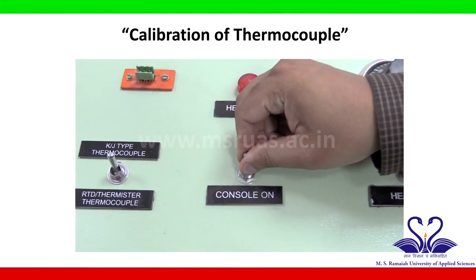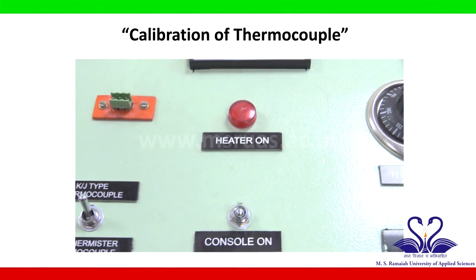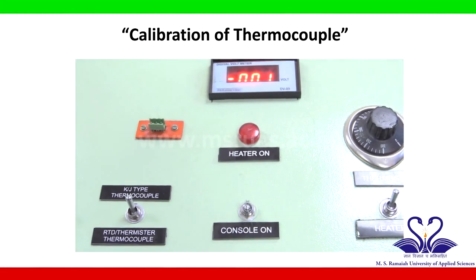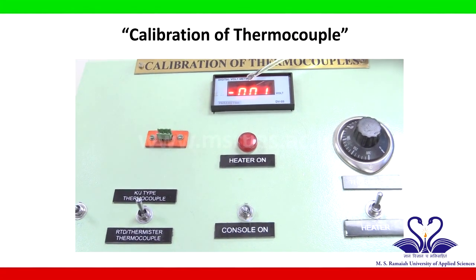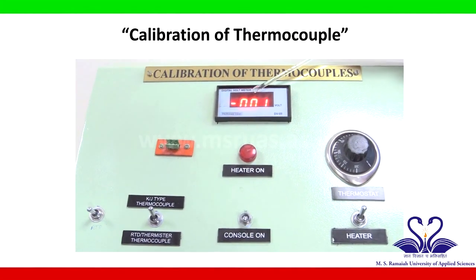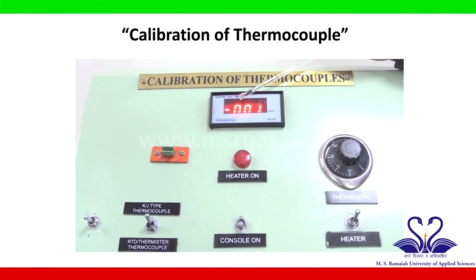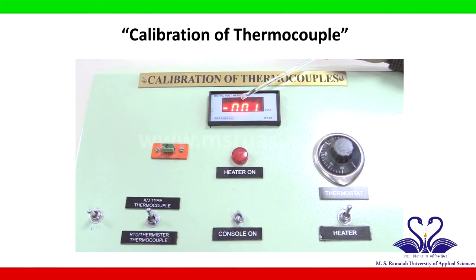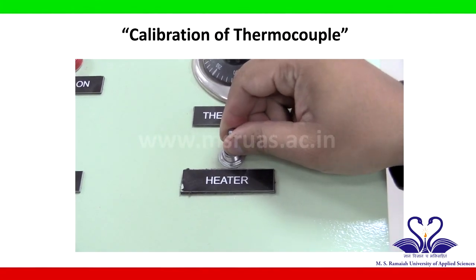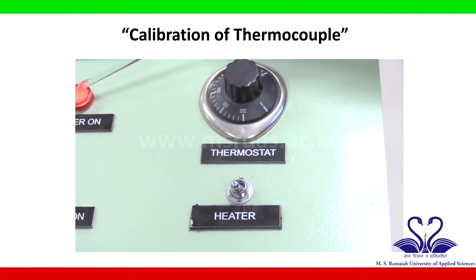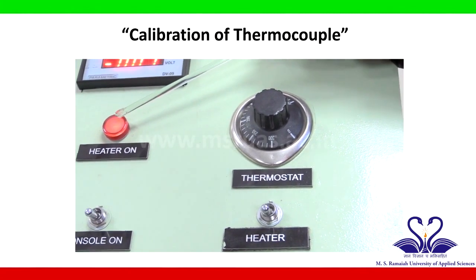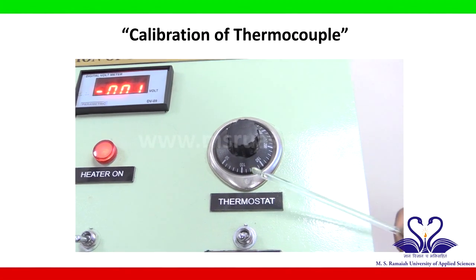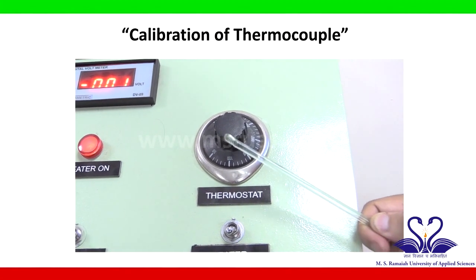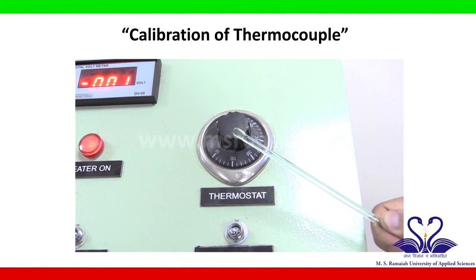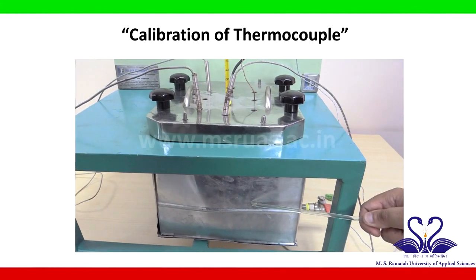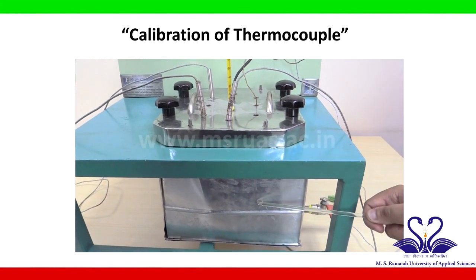Firstly, switch on the console. As soon as the console is switched on, you can see a reading on the digital display. This reading is nothing but the voltage reading. Next, turn on the heater, which is indicated by the red light that the heater is on. Set the thermostat to 100 degrees centigrade so that the heater automatically gets switched off when the temperature of the water inside the bath reaches 100 degrees centigrade.